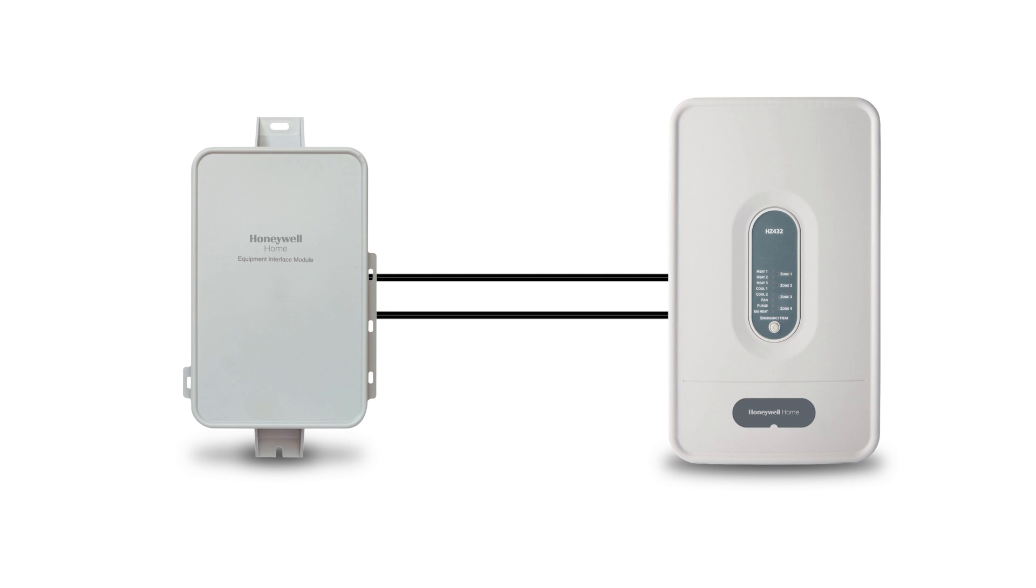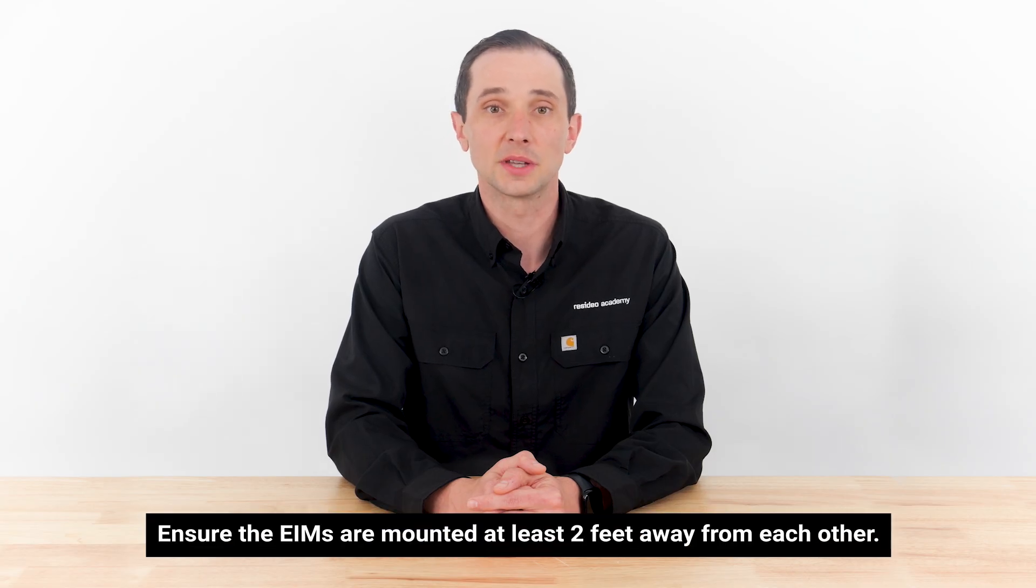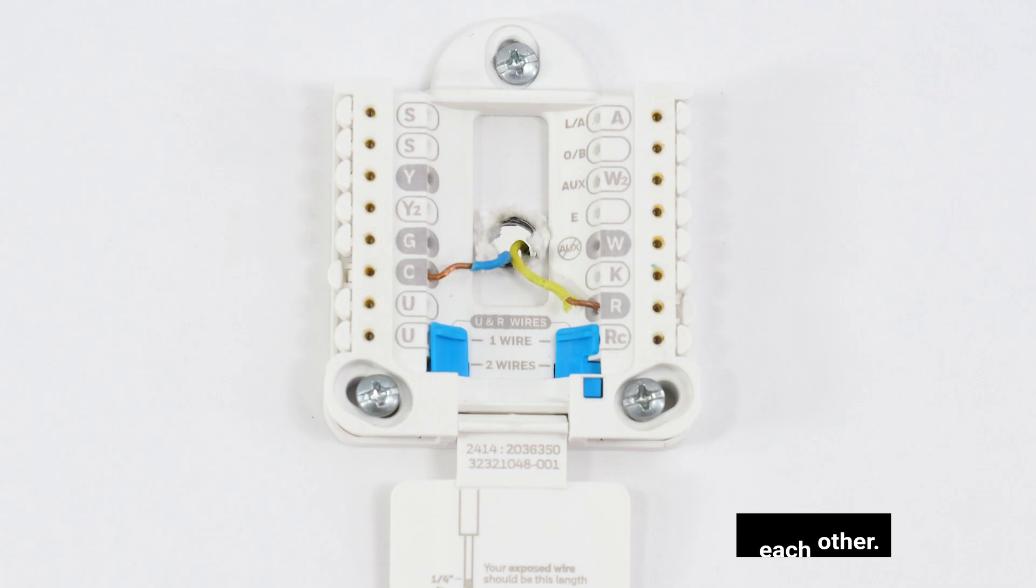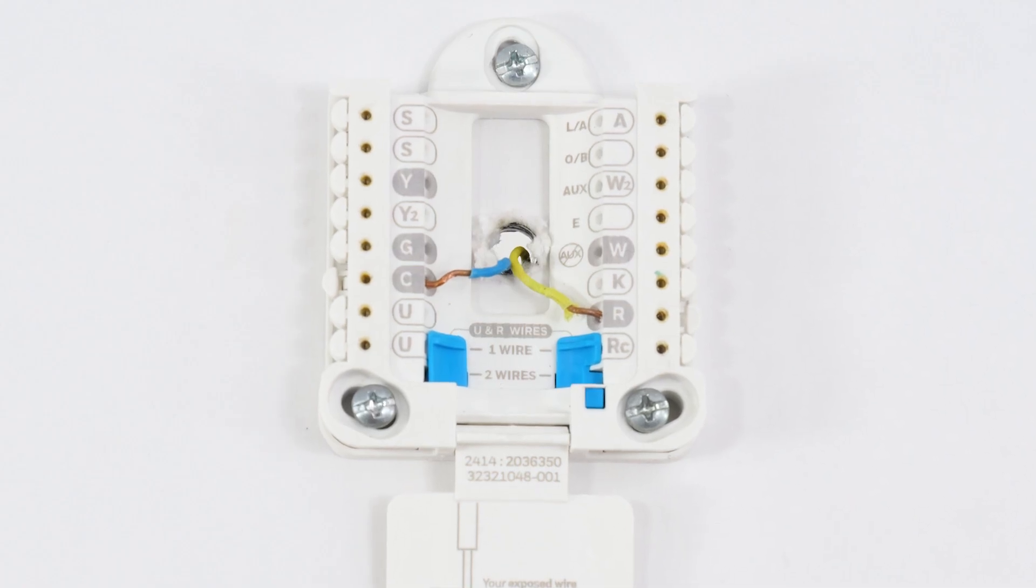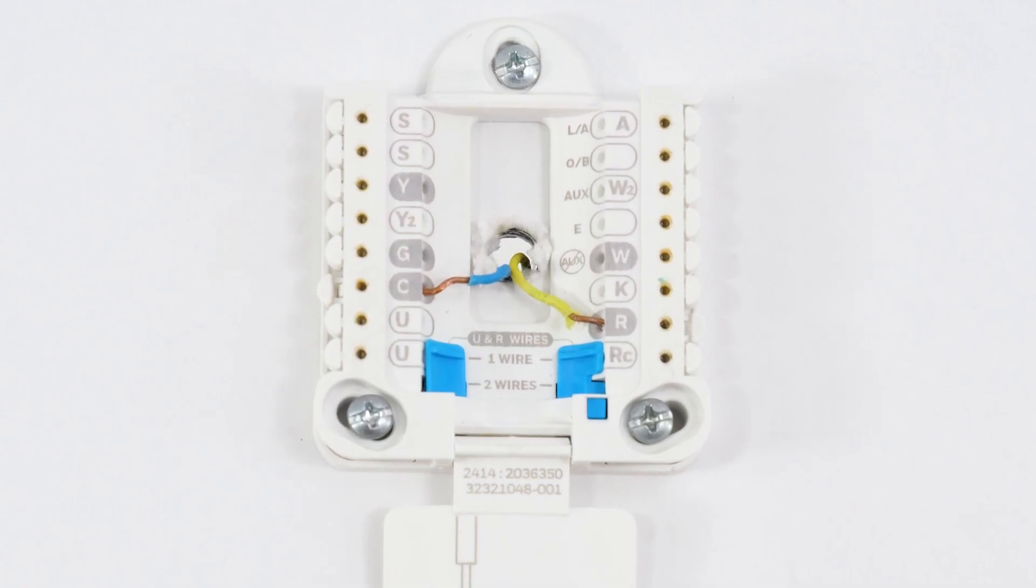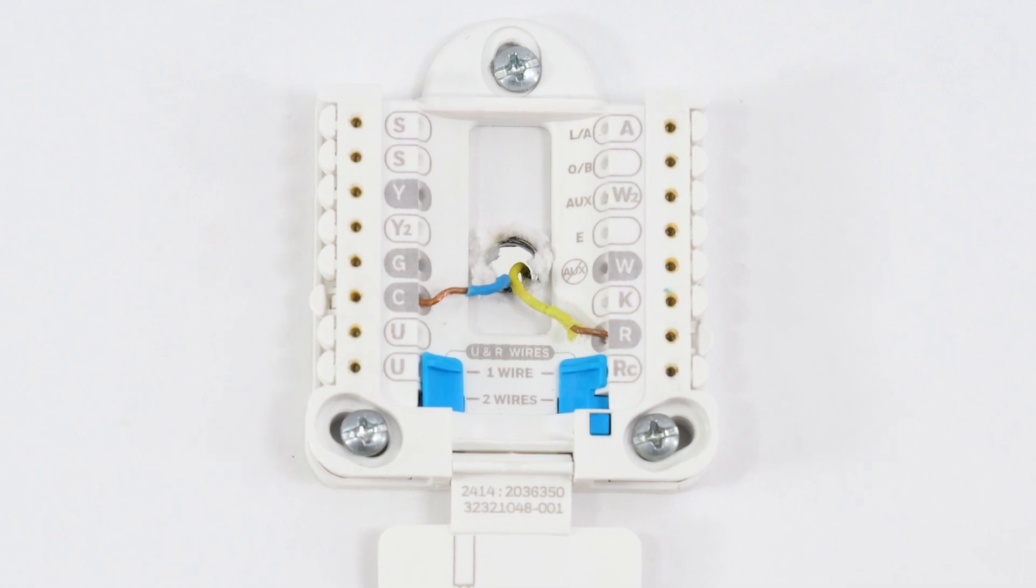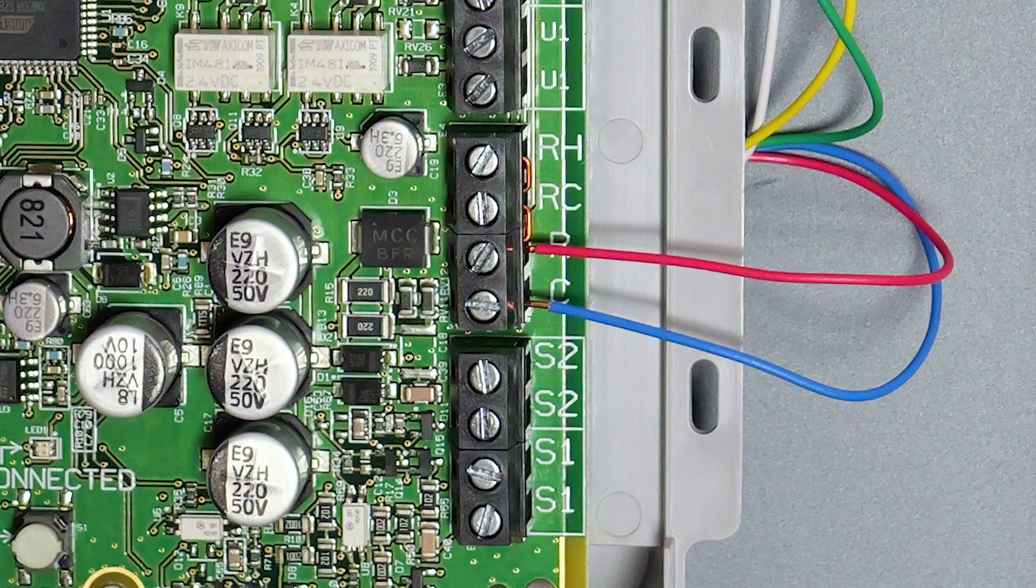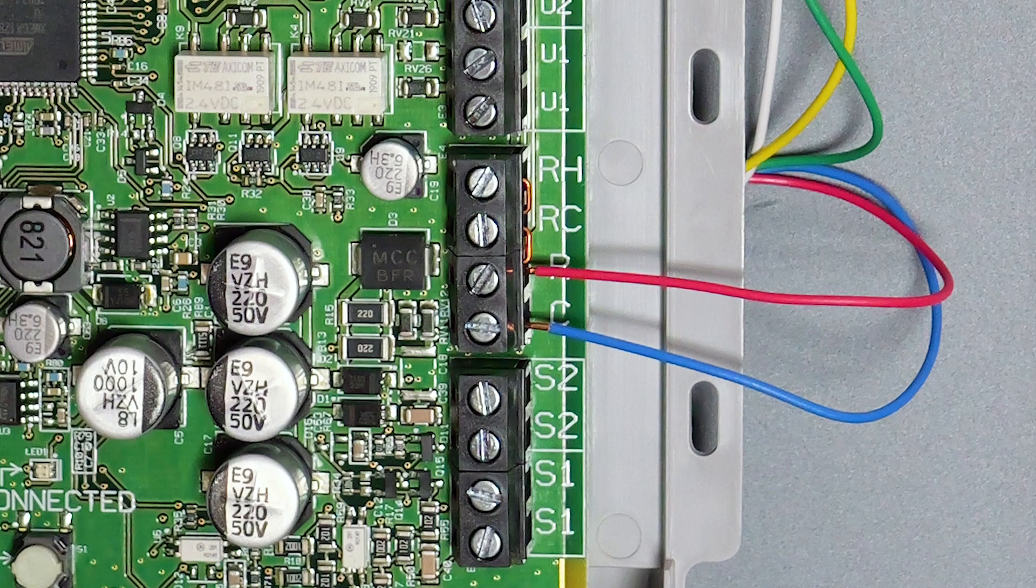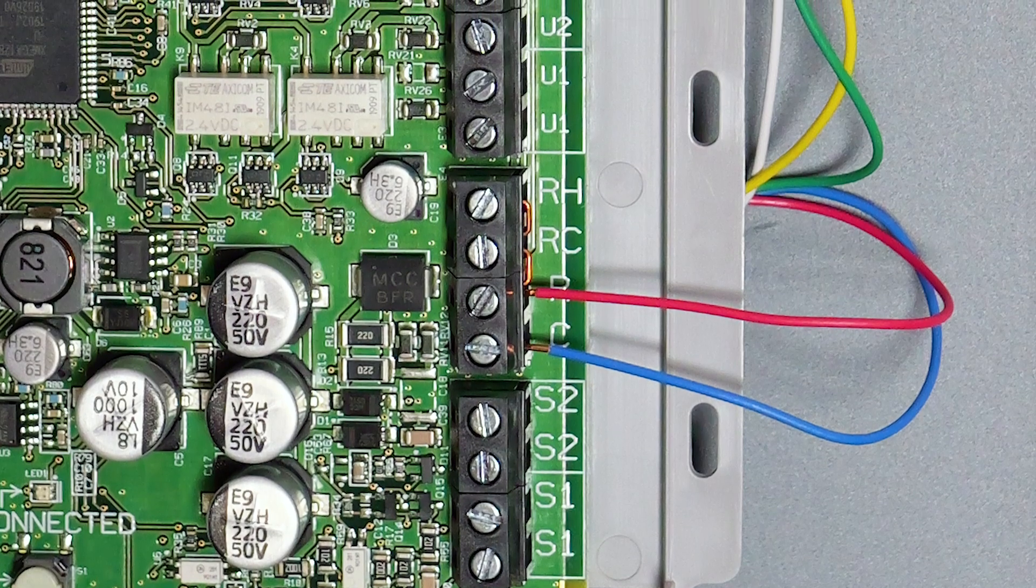To begin, let's mount the EIMs and zone panel near the equipment. At each thermostat location, choose two of your existing wires and connect to the R and C terminals on the UWP. At the EIM, use the same two wires used at the UWP to connect to R and C on the EIMs.